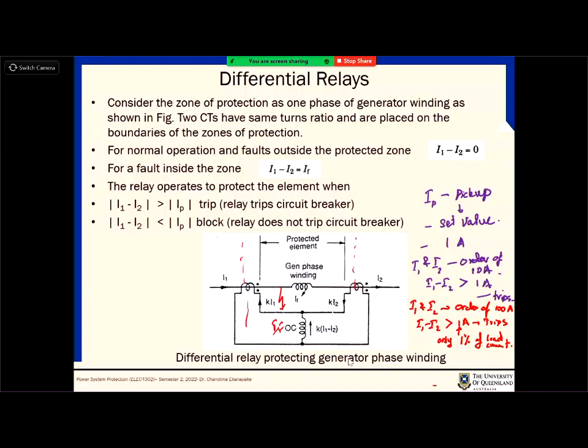That's called pilot relays. They will have that in, and then they will have the traditional impedance protection as well. So if one fails, the other one cuts in, so you don't have to rely on one thing. Yes, time delay, exactly. When you are going with real protection schemes, you don't rely on one technique, and that's why you have very reliable electricity. You are looking at many different factors, because each scheme has its own advantages. And when you combine their outcomes, you can even locate the exact location of the fault.